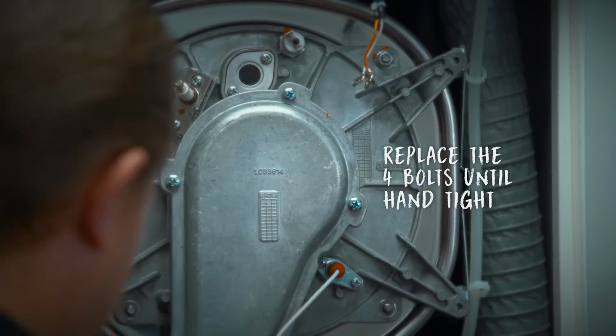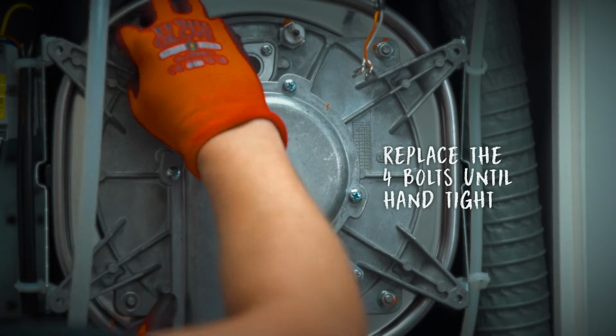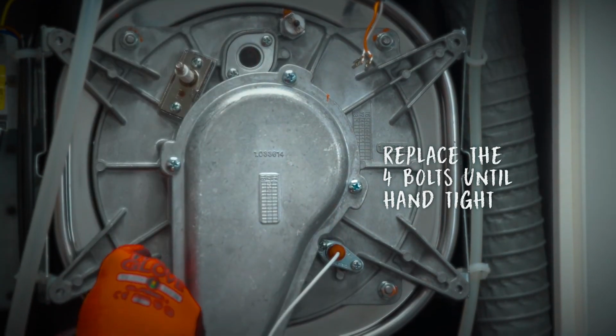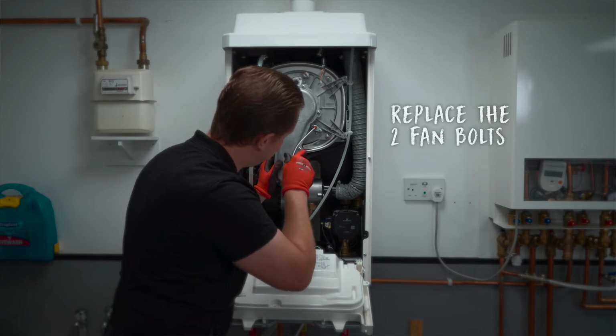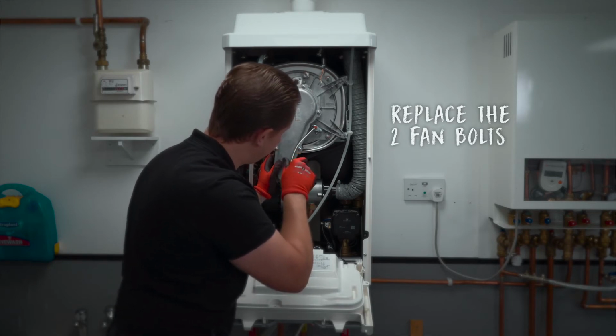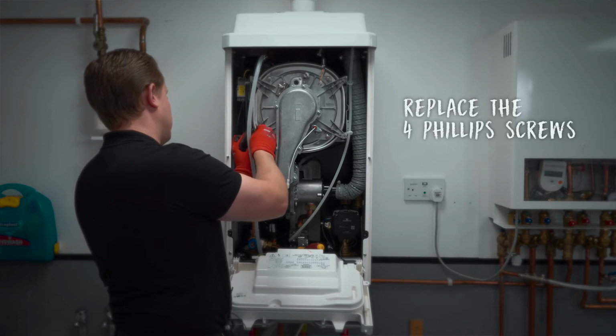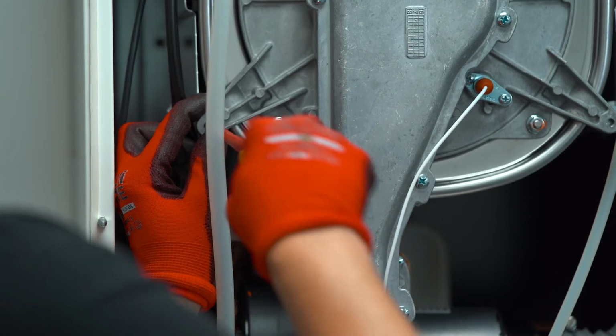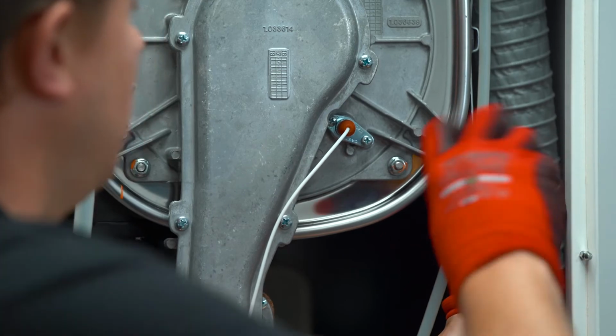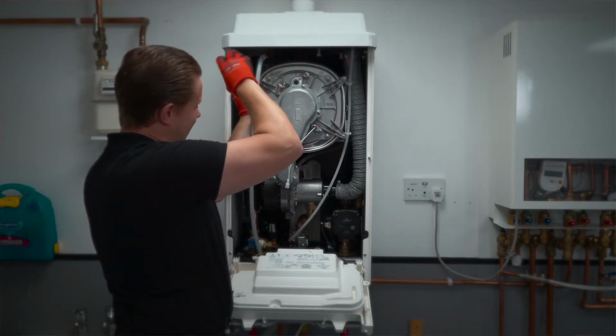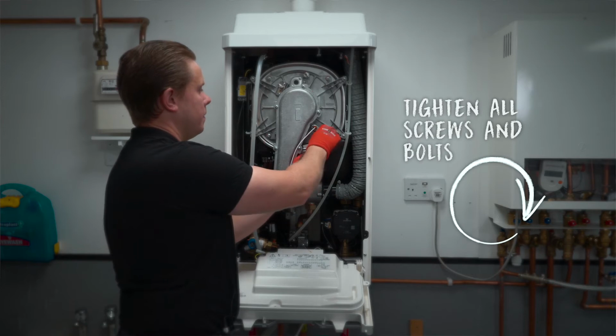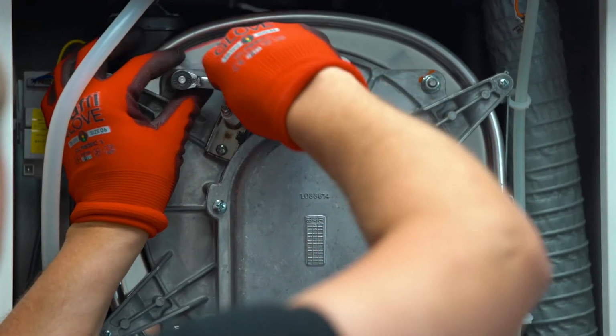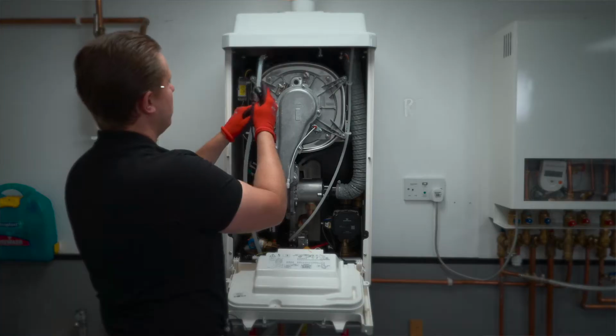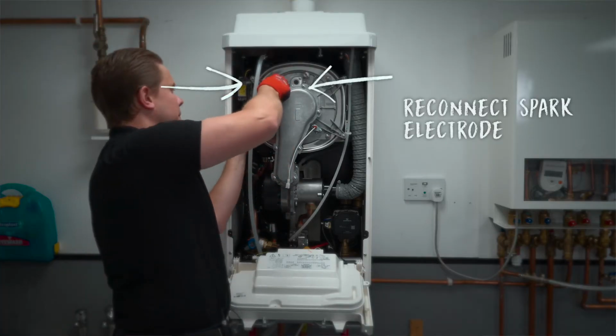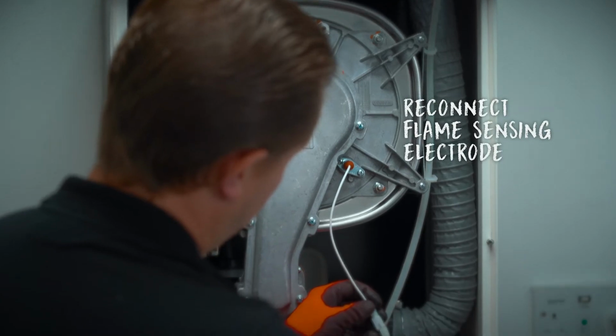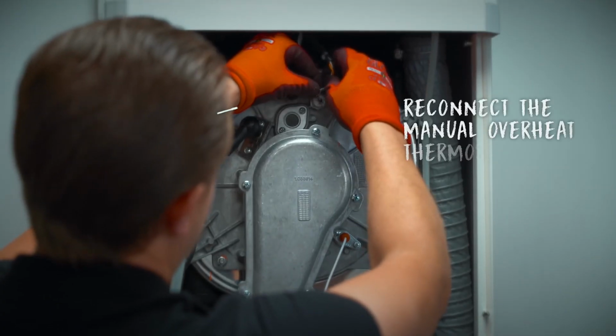To secure the burner in place, reinstate the four 10mm nuts until they are hand tight. Then reinstate the two screws securing the burner to the fan housing and then the four Phillips screws on the outer heat exchanger door. You can then tighten and fully secure the four nuts on the door using a 10mm ring spanner. Next, reconnect the ignition lead to the spark electrode, flame sensing electrode lead, and the manual overheat thermostat.